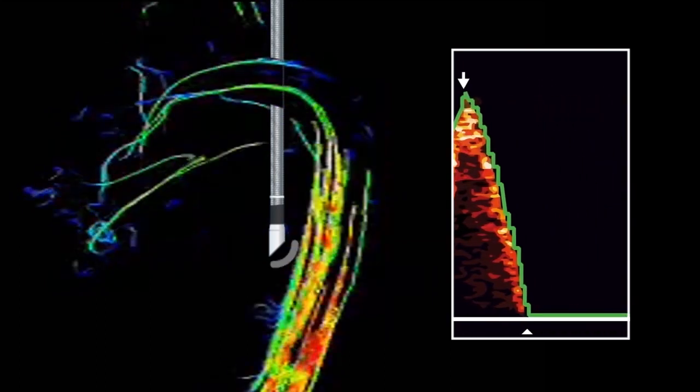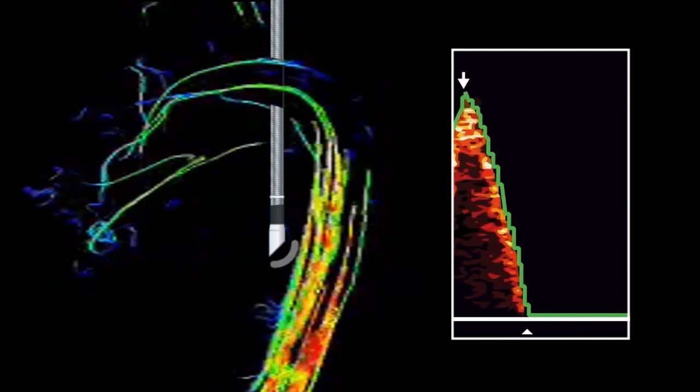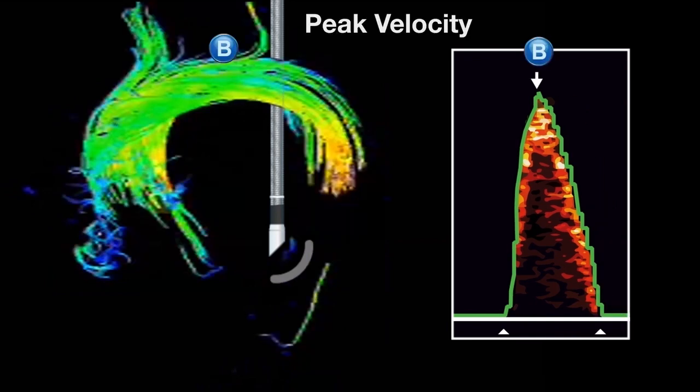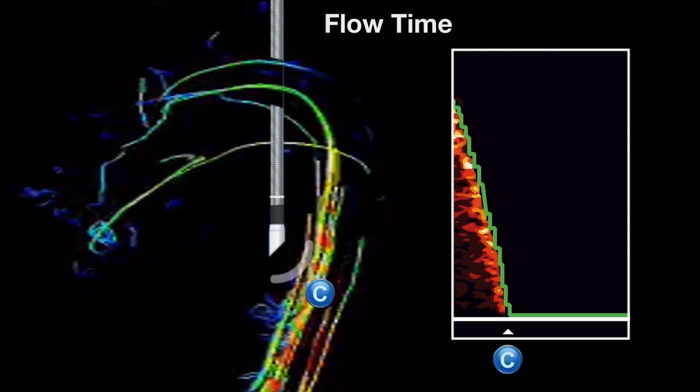Doppler monitoring directly measures blood velocity beat to beat and in real time in the aorta. Data is collected 180 times per second to create the iconic Doppler waveform. Accurate and precise determination of the start of systolic blood flow, the peak blood velocity and at the end of systolic flow enables calculation of stroke volume and other key parameters, giving information of preload, afterload and contractility.